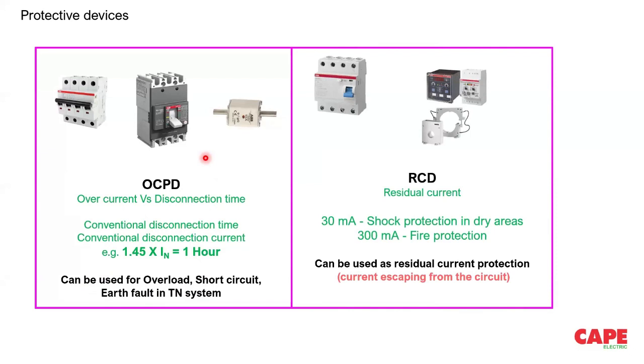Similarly, we have one more protective device which can be used for automatic disconnection of supply during earth fault or earth leakage. This is called an RCD, residual current device. In a residual current device, for example, 30 milliampere is the maximum allowed for shock protection. The residual current for a dry area for 50 Hertz AC is 30 milliampere. Of course, for pure DC, RCDs are not yet available in the market. Still, it's under development. Of course, the current perception is 80 milliampere. It's not 30.